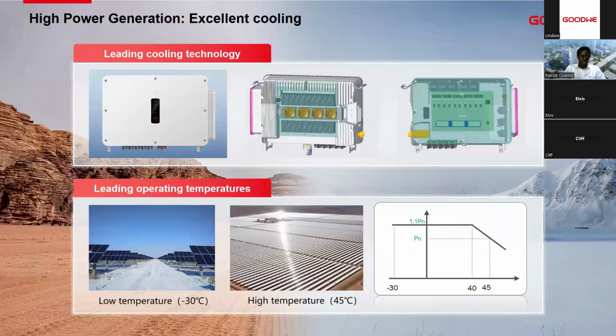In terms of generation, this is what we are able to offer. We have a leading cooling technology, especially on the fans. This is able to dissipate the heat quickly. As we know, electronics require very efficient cooling, and this is able to do that very efficiently. Also, looking at the operating temperatures, the inverter is able to operate at temperatures as low as minus 30 degrees Celsius and as high as 60 degrees Celsius. Therefore, you have a wide temperature range to play around with. As you can see, as long as you are under 40 degrees Celsius, you're able to produce 110% of the inverter. For example, for the 100, you're able to get 110. And it only starts derating from the nominal value, which is the size of the inverter, above 45 degrees Celsius.